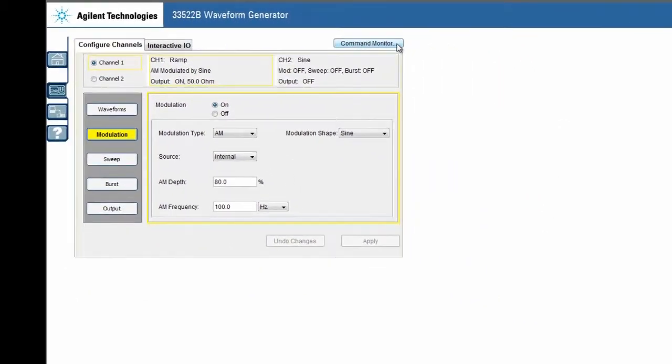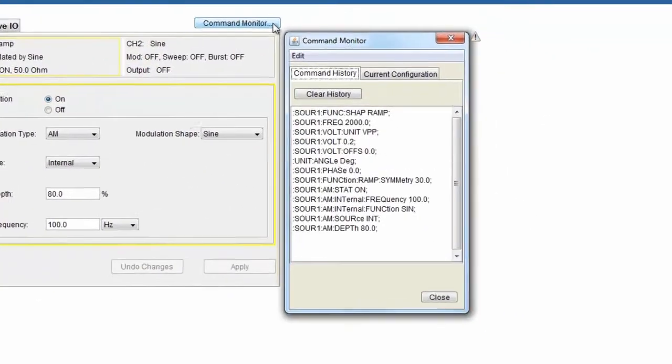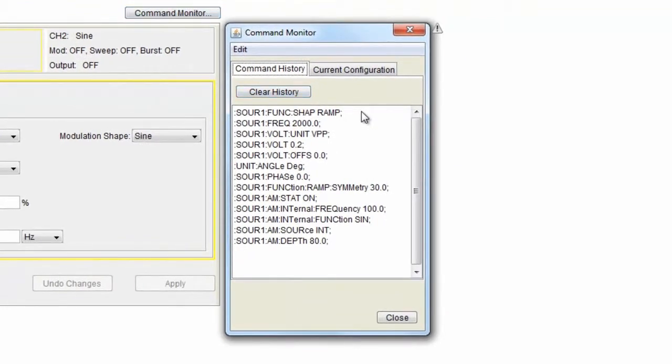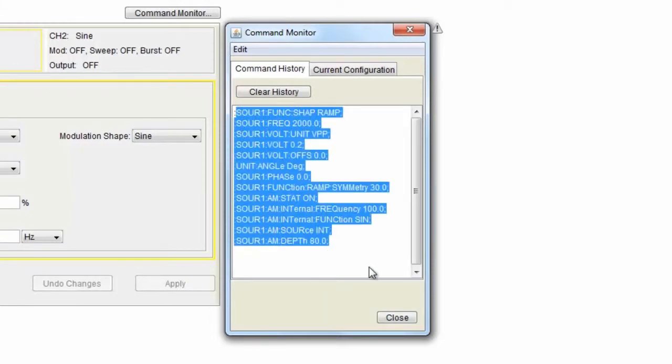One final thing I want to point out is the command monitor. So when I click on command monitor, it comes up with a list in SCPI of all the different commands I've made. SCPI stands for standard commands for programmable instrumentation, and that's what people use when they program these instruments. So you can imagine that you could cut and paste this information here.